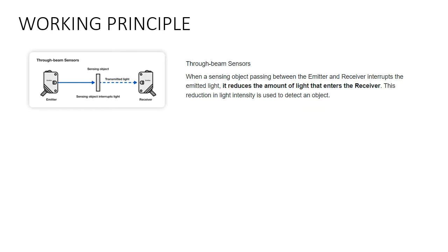In photoelectric sensors there are three different types. The first is the through beam sensor. The through beam sensor has an emitter and a receiver, with the sensing object in between. When the part is not present, the emitted light is received by the receiver. As soon as we introduce a part in between, this continuous beam of light gets interrupted, and thus we get a signal that the object is present.